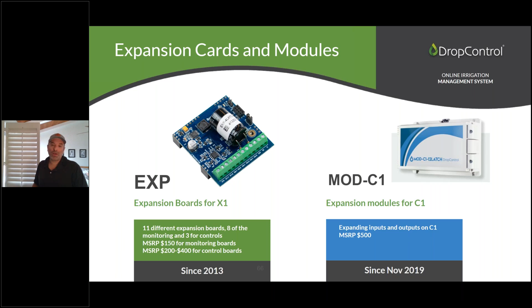The expansion modules and expansion boards are in the hundreds of dollars for the different models. For example, here's a well pump with an existing flow meter and a filter station. We add pressure sensors before and after the filter, 4 valves at the filter station with pressure switches to confirm correct operation, and a CIMIS weather station since it's in California. A system like this needs an RFC1, a couple of pressure transducers, and 4 switches, ending up as a total investment of $4,000 in equipment.